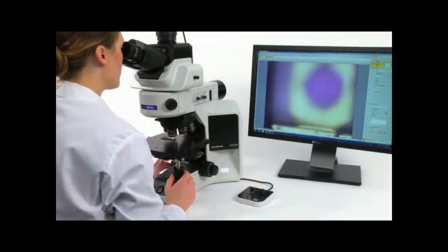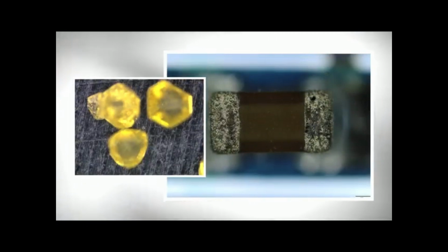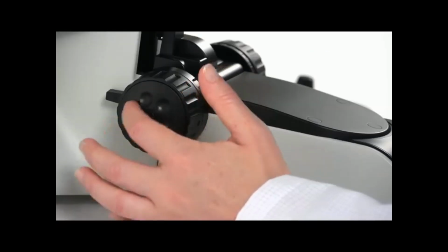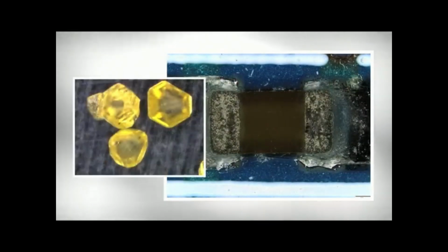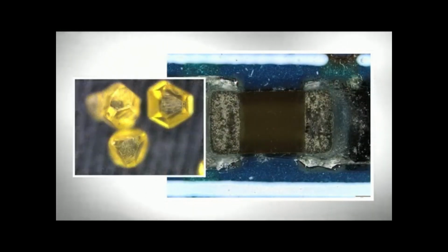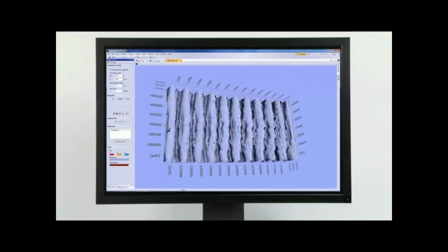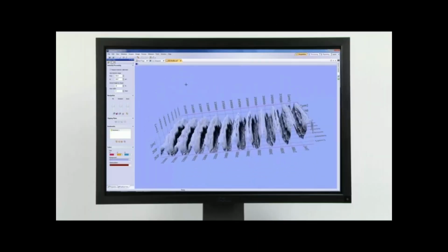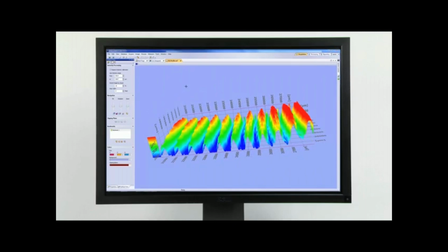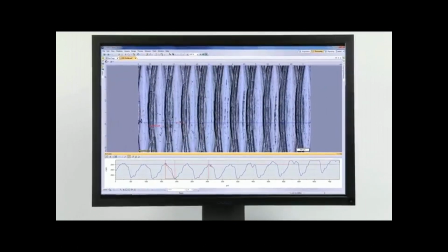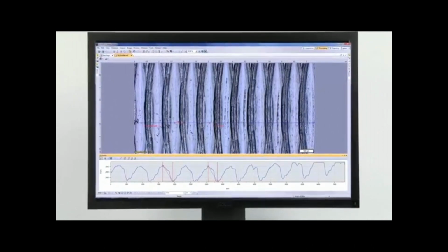When a sample's topography extends beyond the depth of focus, Extended Focus Image, or EFI, enables you to use the fine focus adjustment on the microscope and combine many images taken at different Z levels to create a single image that is entirely in focus. This acquisition can be viewed as a 3D image at various angles and as a color map. When using a Z encoder, measurements can be performed on the profile.